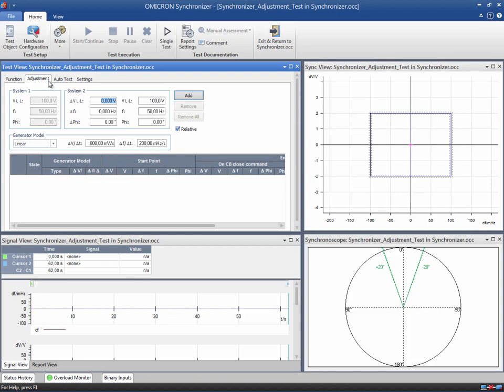In this case, 40 mHz and 0V. However, keep in mind that the relay will issue the close command as soon as all the conditions are met, whether the target point has been reached or not. The module will check that the time elapsed between the start signal and the CB close command is within the maximum synchronization time.